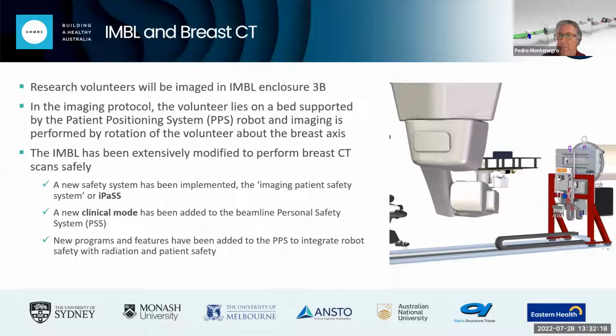And when I say develop, it means we had to do the design, we had to design the hardware. A PLC, programmable logic controller team, had 2 or 3 engineers working on this for many months. And then we added a new clinical mode to the personal safety system on the beamline. The personal safety system of a beamline is what makes sure that nobody can receive any radiation at all. It basically works on the assumption that nobody will be in a radiation room with X-rays on.